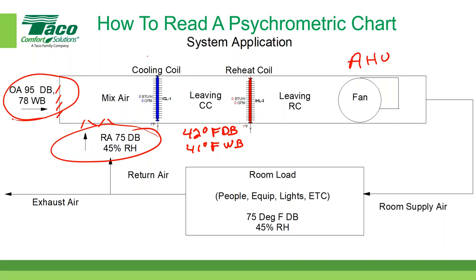So this cooling coil is cooling and dehumidification. I'll put DH for cooling and dehumidification. CDH, yeah, cooling and dehumidification. I can put an and here. And then the reheat is sensible heating.